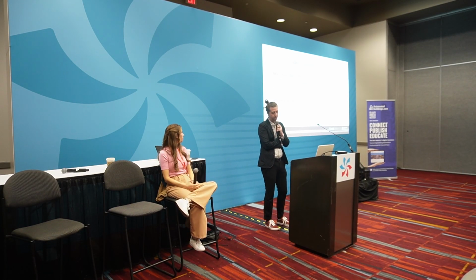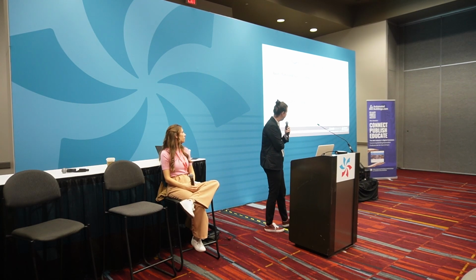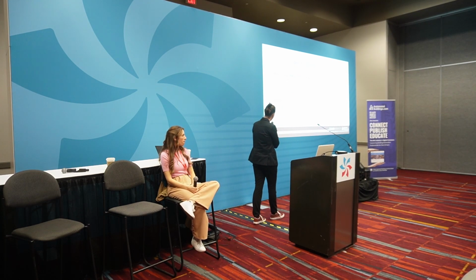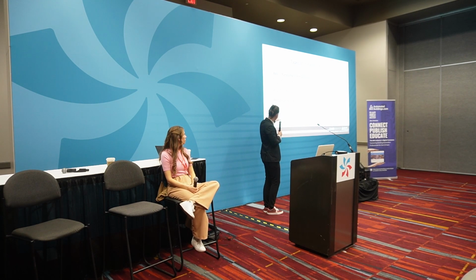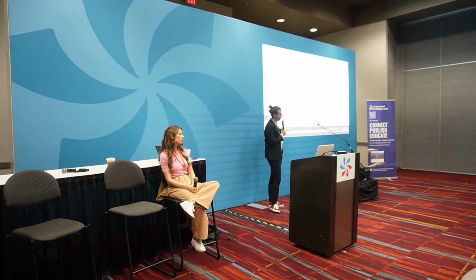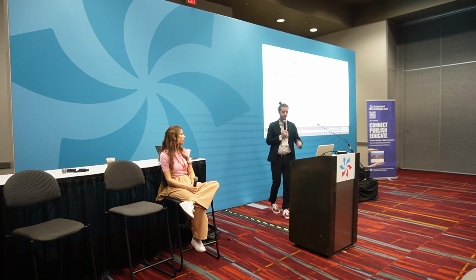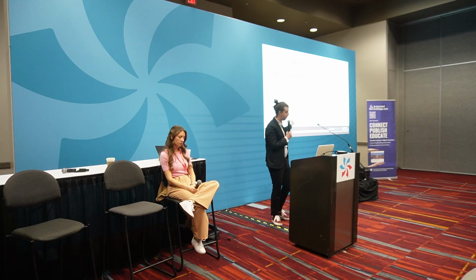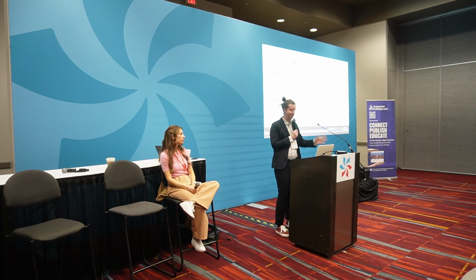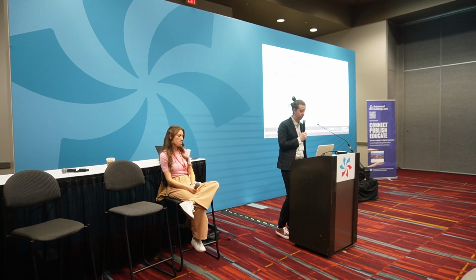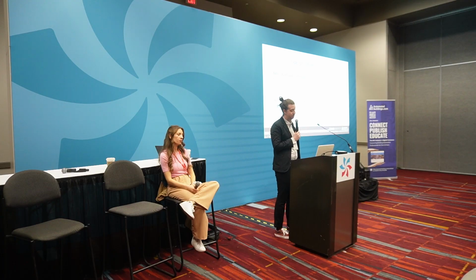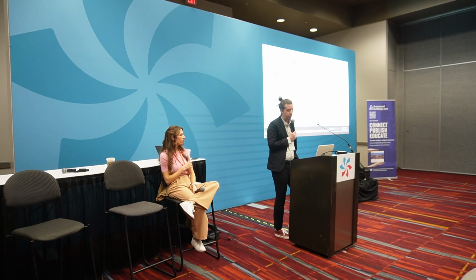I think what's important is that we've also used different terms. Performance commissioning can be done on a new system, where you're installing a new piece of equipment. It can also be done as a recommissioning process on an existing building, or on just one system within an existing building. You don't have to recommission a whole building at a time.